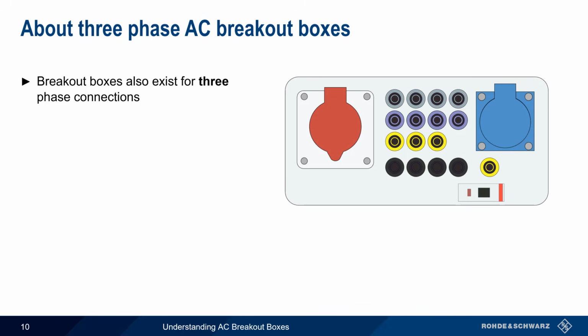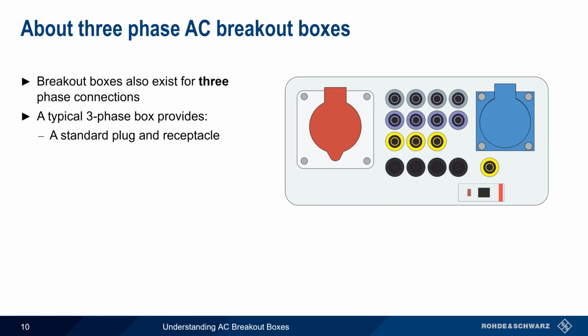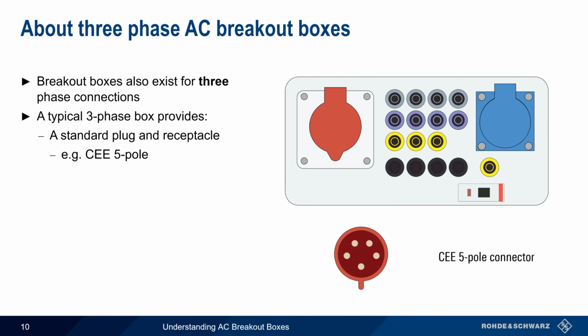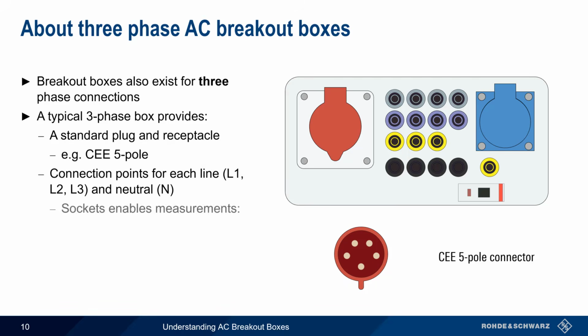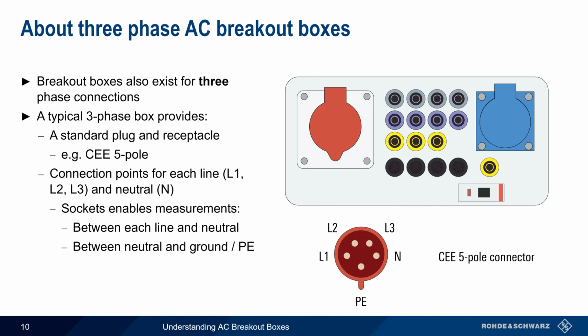Before we conclude this presentation, let's talk briefly about 3-phase AC breakout boxes. Like single-phase boxes, these typically provide a standard plug and receptacle, such as the CEE 5-pole connector shown here. They also provide sheathed banana plug connection points for each of the 3 line conductors, as well as for the neutral conductor. These sockets can be used for measuring between each line and neutral, as well as between neutral and the protective earth or ground. It's also common for these types of breakout boxes to contain an integrated circuit breaker for safety.